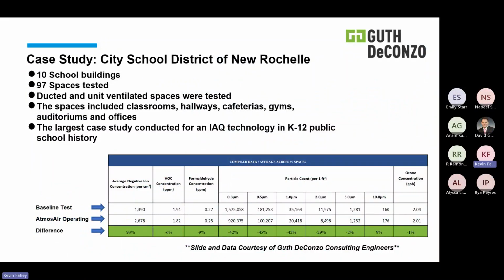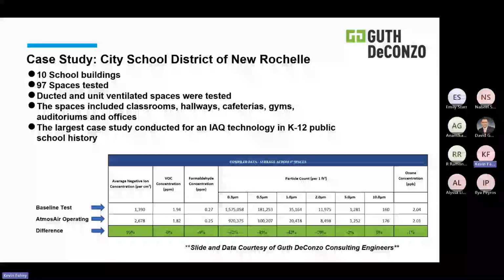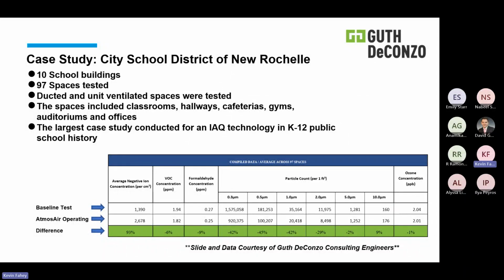This is a case study that was done by Guth DeConzo, an engineer out of the Albany area, for a school district, New Rochelle. It's in Westchester County in New York State. Part of the contract between the dealer who installed this and the school was they wanted to test 10% of every space to make sure that the system was working. So they tested 97 different spaces and showed the baseline. The requirement was they had to show an improvement in ion levels inside the space. They had to show an improvement in particle levels inside the space. They had to show an improvement in VOCs and formaldehyde concentration. And there could be no ozone.